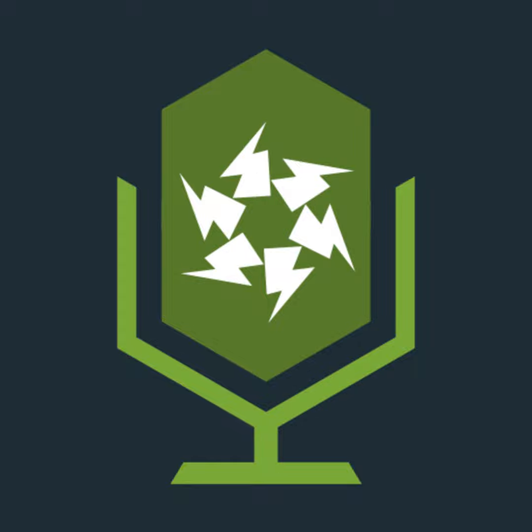Okay, we get the value of volt drop from the part in the cable selection chart that we saw earlier on, the millivolt per amp per meter, and we're going to use that in an example very, very soon. But we must verify the volt drop. Now, there is a table in Appendix 4, 4AB, which is just after the reference method table, I think.